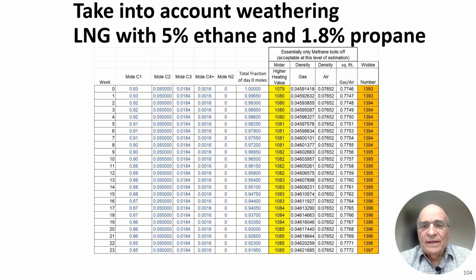LNG that's stored in an LNG tank will weather over time, and its composition will change. And that is because the way LNG weathers is that its most volatile gases preferentially boil off. That's not sequentially, that's preferentially. When I say preferentially, it means like, let's say you had a tank that had methane, ethane, and propane. All three of those will boil off, but the methane will boil off at a much faster rate than the ethane and the propane. And that's because the methane is more volatile. If nitrogen was in there, then the nitrogen would boil off preferentially more than even the methane.